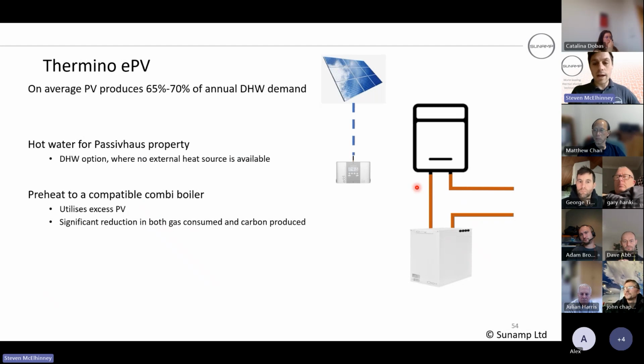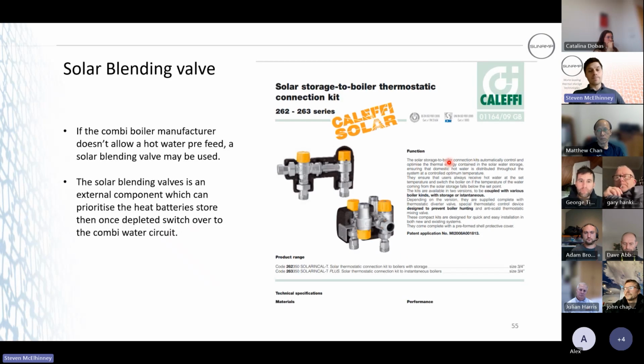But if you don't have as much PV being generated, again, the temperature of the battery is starting to drop. The boiler will fire up, but at a lower gas rate, and then it's just making up the difference. So instead of firing up for 30 kilowatts, it's maybe only firing up for 10 kilowatts an hour. So again, the customer's still making a saving there. If you want this configuration but the boiler manufacturer doesn't allow it on that cold water inlet, you could fit a 5-port solar blending valve.